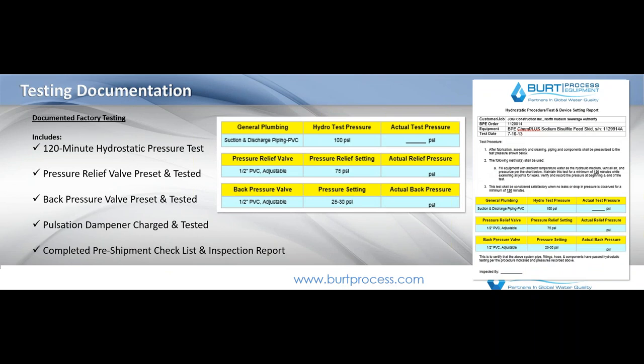All of these systems are thoroughly tested, and the test report is all available. It's very important when dealing with these things because you can be dealing with very strong chemicals — 50% or 93% sulfuric acid, hydrofluoric acid, different chlorides. It depends on what you're pumping, but it's very critical because leaks in these systems become a serious issue. All these systems are given a two-hour hydrostatic test, pressure relief, back pressure, and pulsation checks. Very often on site they're given startup training as well. Leak detectors can be involved, and all the chemicals are usually engraved on the equipment so you don't inadvertently utilize them on the wrong chemical, which can cause catastrophic reactions. Safety plays a lot of role with these types of technologies.